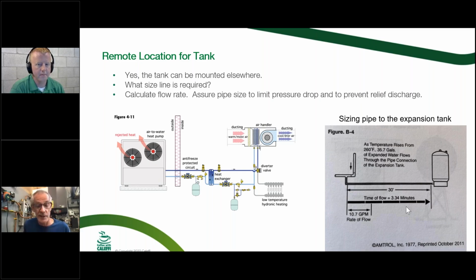There's an excellent example in the Amtrol book, a 7,000 gallon system running at 260 to 270 degrees F. It's pressurized, I think it's 65 pounds or something like that. Under those conditions, it took a 1.5 inch pipe, because you have to be able to accept the expansion, the 35 gallons that system's going to expand when it goes through that temperature differential, through that pipe, without raising the pressure so that it could pop the relief valve in the system. It turned out to be about 10.7 gallons a minute that has to be able to move through that pipe without causing a restriction that would make the pressure go above the relief valve.